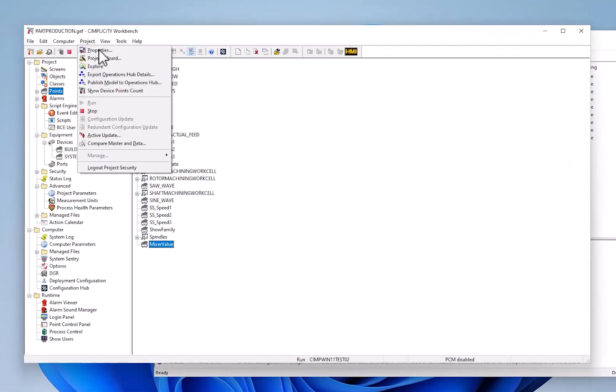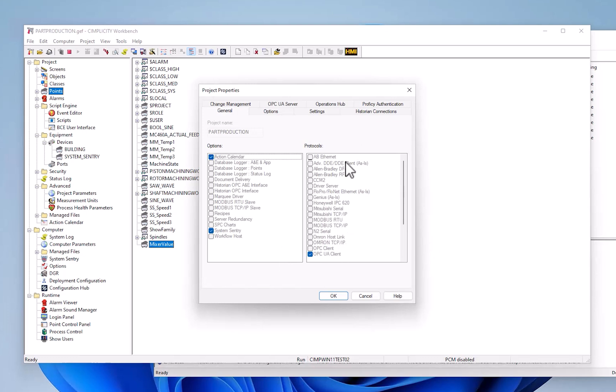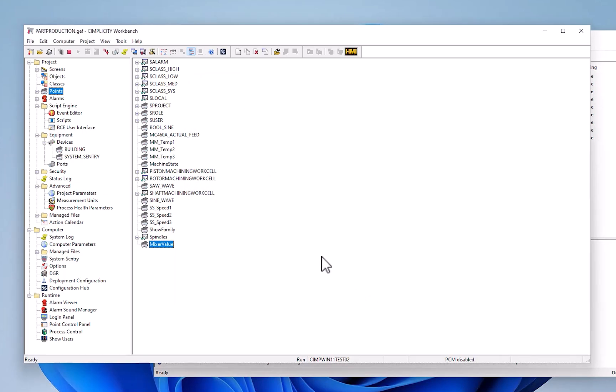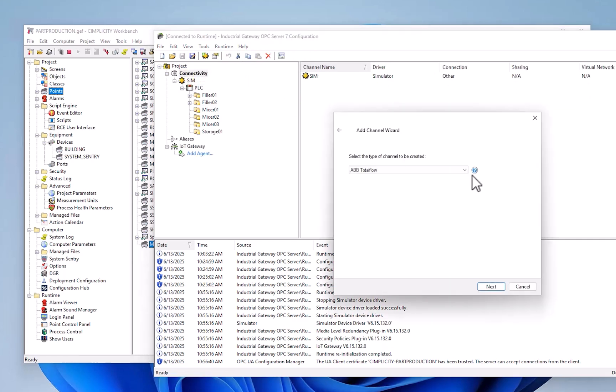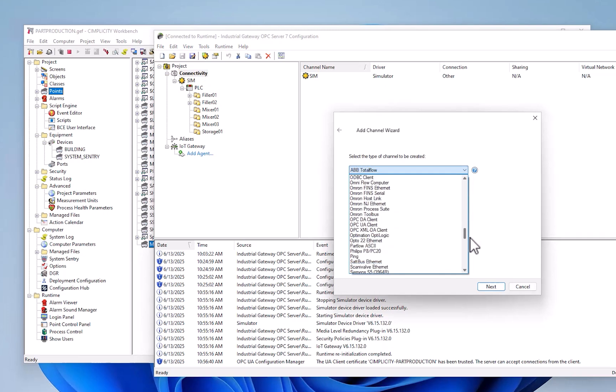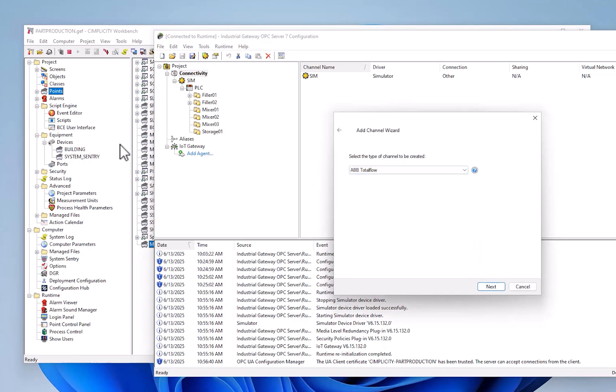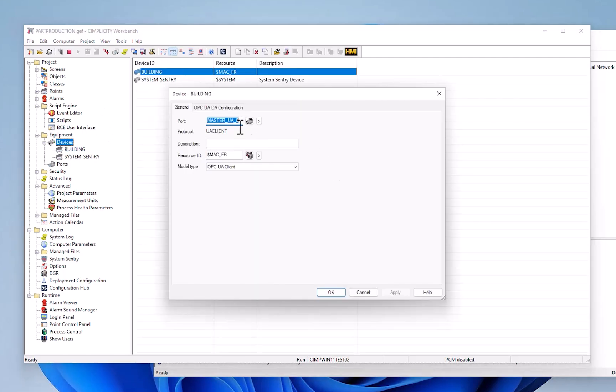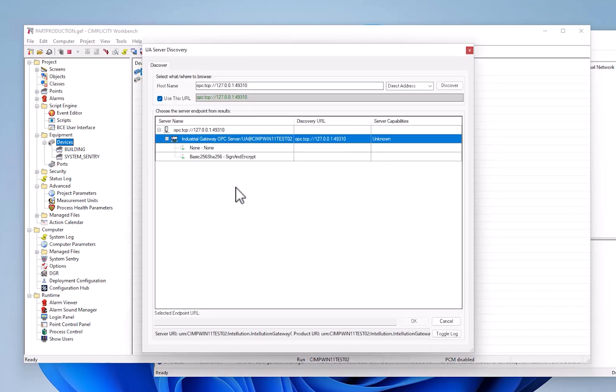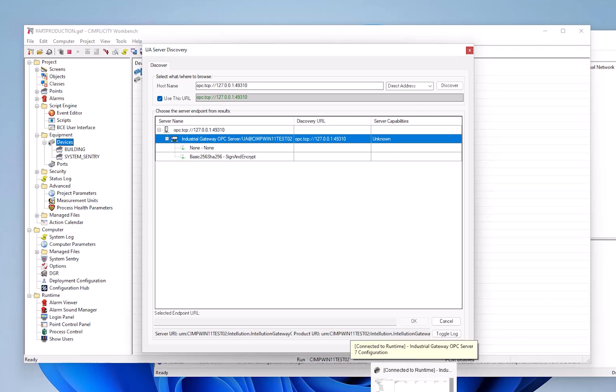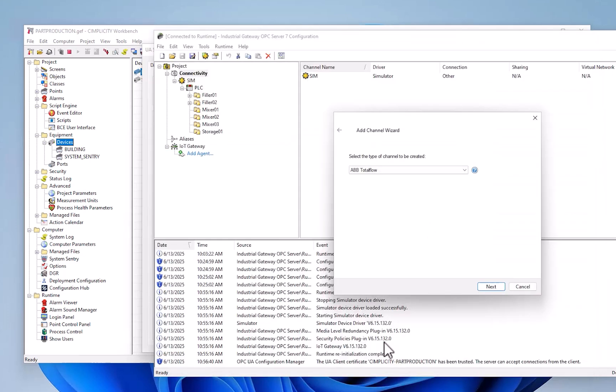CIMPLICITY provides connectivity to many native drivers and protocols out of the box that you can select in the project properties. If those don't match the protocols you need, you can use the IGS Gateway Server to connect to many different types of protocols. As you can see, there's an extensive array of supported protocols through the gateway server, which you communicate to using the OPC UA client in CIMPLICITY to talk to the IGS server. We're connected to this gateway server and retrieving values from the SIM device for this demo.